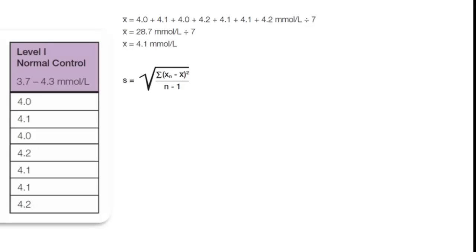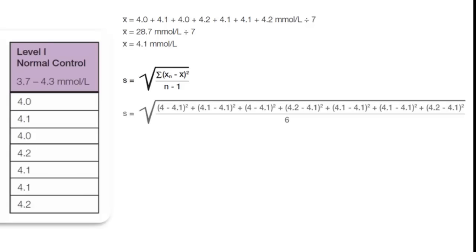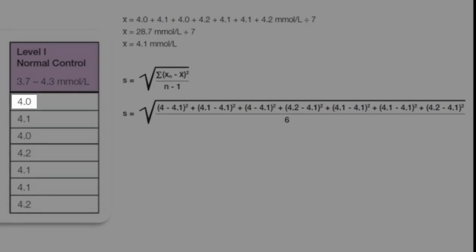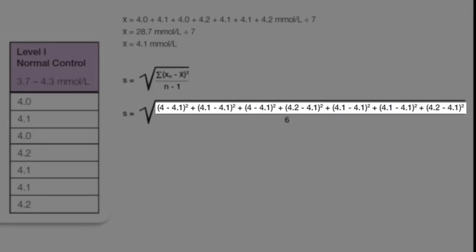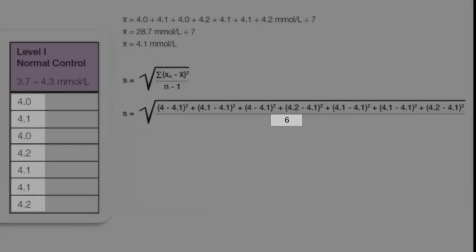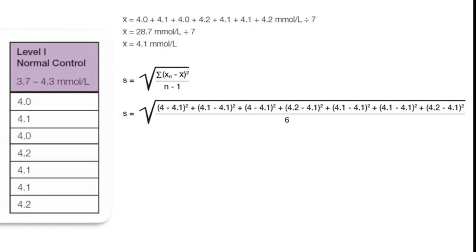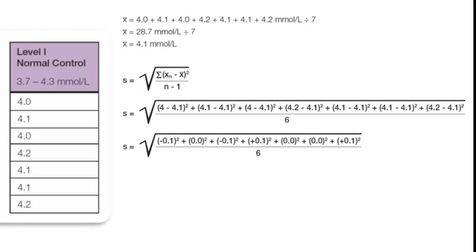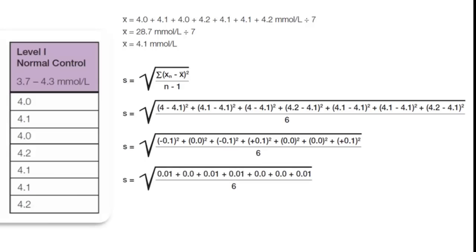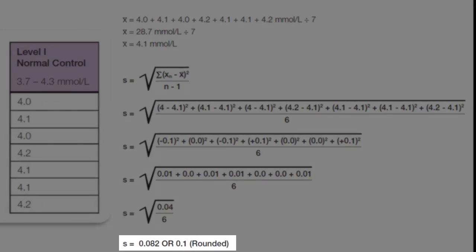First, enter the values into the formula. The value to the left of the minus sign comes from the dataset, and the value to the right of the minus sign is the mean that was just calculated. This pattern repeats for all of the points in the dataset. The divisor is the number of data points in the dataset minus 1. The subtraction is done within the brackets, the values are squared, and then added. Finally, the division occurs and the square root is taken. The standard deviation for one week of testing of the normal potassium control level is 0.082 millimole per liter.